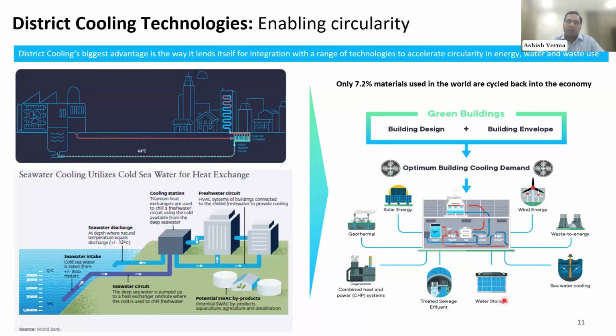What helps us in optimizing is the passive design of the building when the building is being designed. There are passive measures, including green building measures, which are incorporated, which help us reduce or optimize the cooling demand for a particular building. And when the demand is optimized, then we go for district cooling integration to supply the cooling. For a district cooling system, there are multiple avenues which could be integrated. The first is solar energy. We heard from Dr. Garg how solar energy was integrated into the cooling system.